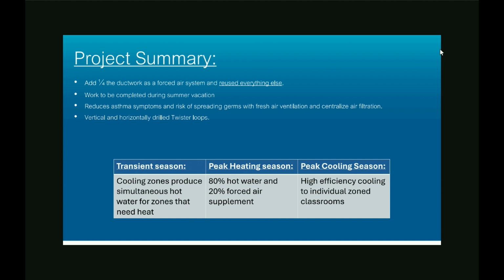And then during the peak cooling season, somebody's about to raise their hand, hopefully, and say, well, hang on, we're not going to be able to get the full capacity if we only put such a small ductwork in. We're not going to be able to do full cooling. That's probably true. But also, this is upstate New York. This is a school. And some amount of cooling is a lot better than no cooling. And so even though you can't necessarily cool down the rooms to 65 degrees, you might be able to definitely take it from 90 degrees down to 80 or 70, 77, something like that. So you're still getting most of the benefits.